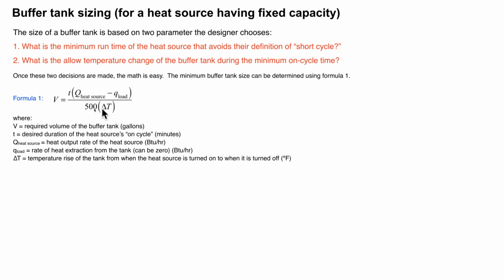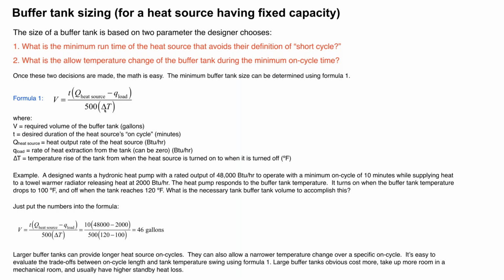And then we divide by a factor of 500 that's related to the heat capacity of water. And we're also dividing by how much of a temperature change that buffer tank is going to undergo from when we turn the heat source on to when we turn it off. And I'll give you an example here.